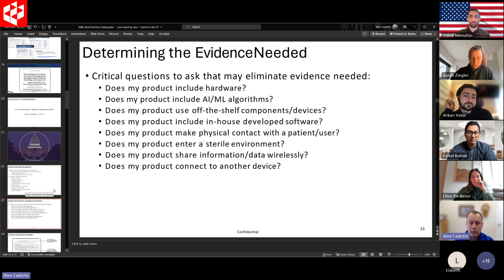And does my product connect to another device? That's partially cybersecurity, but it's also meaning that you're going to have to account for the risks of that device that you might be interacting with. So clinical validation testing, for devices that don't have a pretty straightforward bench testing requirement. A lot of times you have to run that study. You may have to collect clinical data. There's a whole process of basically, especially for riskier devices, that you have to do an IDE with FDA. I don't have a huge amount of expertise with IDE because most of the time software devices don't require an IDE. It's not always true, but most of the time.